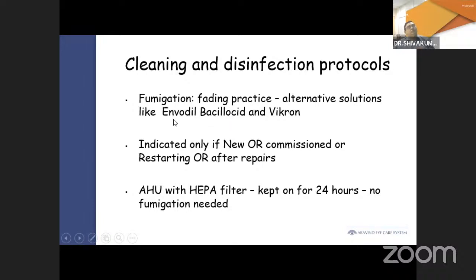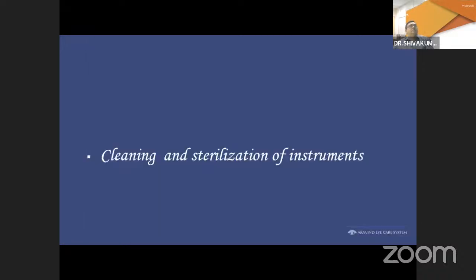There are alternative solutions available like Envodil, Bacillocid and Vikron. But then ideally it is indicated only if a new operating room is commissioned after 3 consecutive negative culture reports, or if you are starting an operating room after construction or repairs. And if we have an AHU with a HEPA filter, which is kept on for 24 hours, with the AC not functioning during the time that surgery is not on. But if the AHU is on for 24 hours in the blower mode, no fumigation is needed.